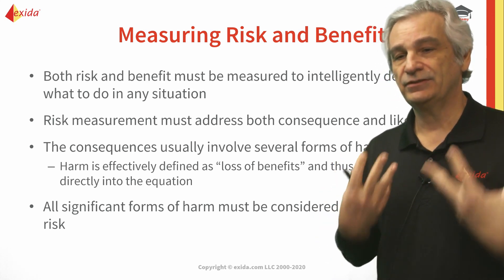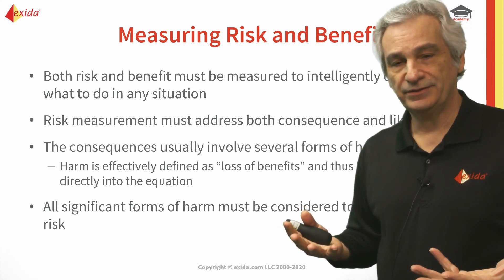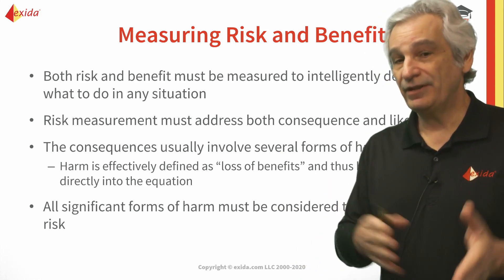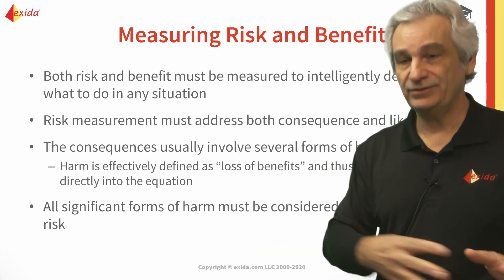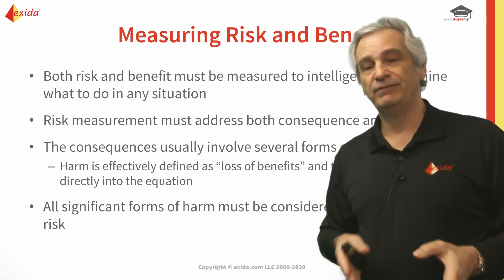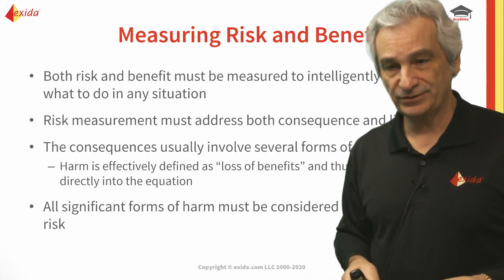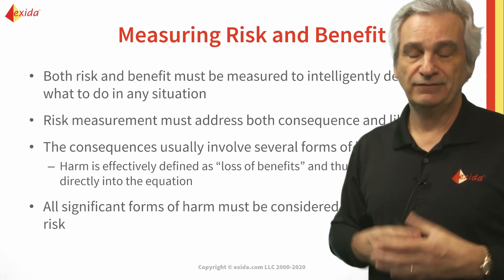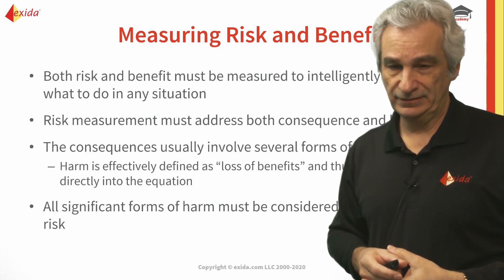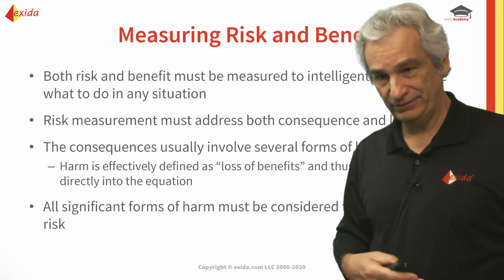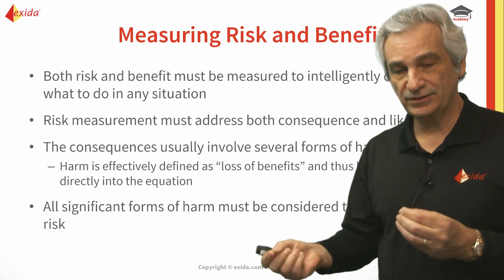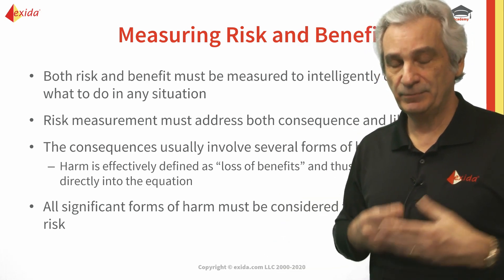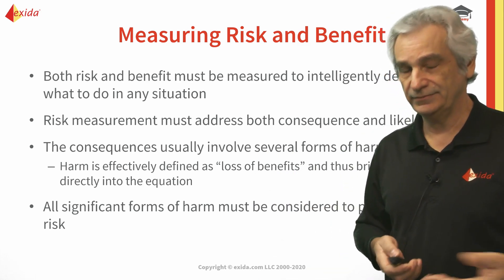For example, if we just focus on consequence, we might have a very high consequence - a plant explosion with multiple fatalities. But when we look at the likelihood, it might be very low. So a very large consequence combined with a very low likelihood may bring the overall risk down into an area that doesn't need too much focus. We can rank severities of consequences and look at likelihoods - highest to lowest - and then consider consequence and likelihood together to determine what that poses in terms of potential risk, and how we address it. We'll go into more detail when we discuss likelihood analysis and Layer of Protection Analysis.